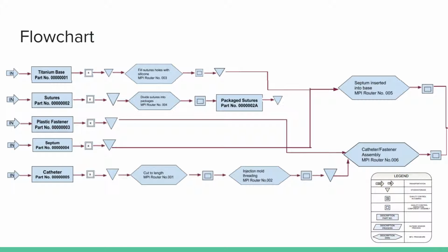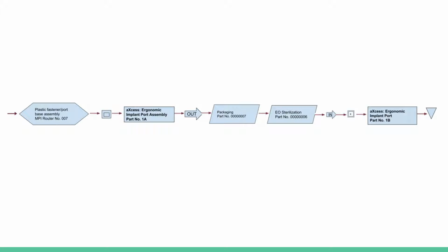So once the parts reach our facilities, all materials must undergo an incoming inspection and go into storage. We'll pull each part when needed for assembly and have a quality control inspection between each step. We expect most of our production and assembly would be completed in a single run since most of the machining and fabrication was done elsewhere. Once we have a final part, we will give it a new identification and send it out for packaging and sterilization. Once we receive the packaged part, it will undergo another incoming inspection and go into storage.